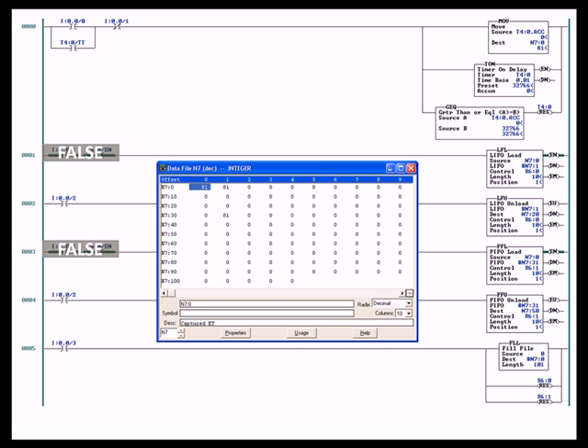When the timer reaches 32,766, the greater than or equal to instruction is true and it resets T4:0. Therefore T4:0 will never overflow. It will just continually increment or accumulate from zero to 32,766, reset back to zero and do that continuously as long as the rung is true.